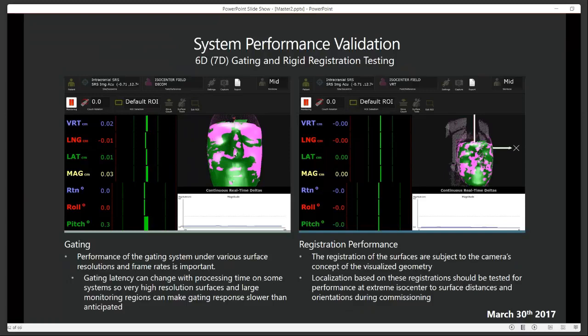Rigid registration performance, again, rigidly registering a surface to a rigid Phantom, not very difficult, very easy, very, very high precision. As you can see in this image, they're all zeros. We would expect them to match very well. You do need, though, to check at extreme positions, at the extreme edges of the field of view, because these are model-based calibrations of these cameras. So the geometry is based on a model-based calibration. And so the extreme edges of the field of view are places where you can find discrepancies, and extreme distances from the surface to the IsoCenter location.